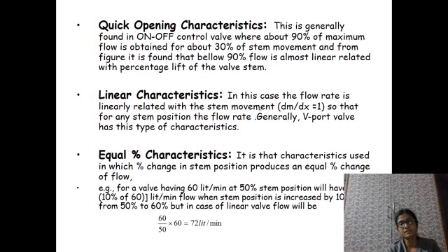Linear characteristics where dm/dx is 1. The flow rate is linearly related with the stem movement, so that for any stem position there is a proportional flow rate. Generally V-port type valve has this type of characteristics, which is normally used for 3-term controllers, PID controllers.